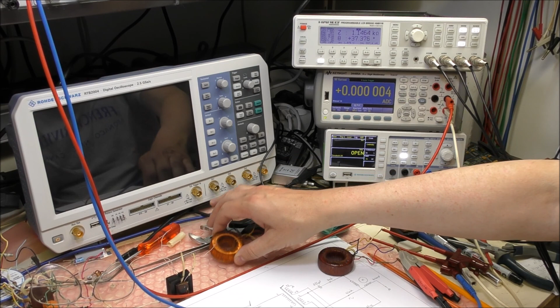It is not possible to do some tests at this moment because one transformer is not operational, one winding is open. So maybe I can see if I can place another winding on this transformer. It depends on the turn number, but maybe the turn number for this winding is not so high. If it is 100, it can be possible, and fortunately I have the second one, so I can make some comparison. I can measure the ratio first, and maybe after that it can be possible to do some tests. I don't know, it will depend if I find the time to do that, because I already spent 2 or 3 days on this.